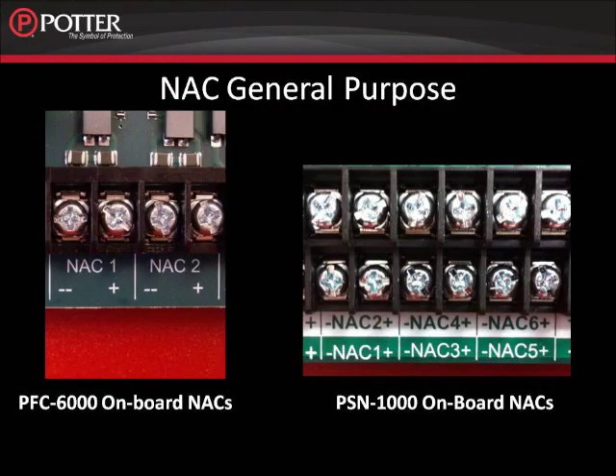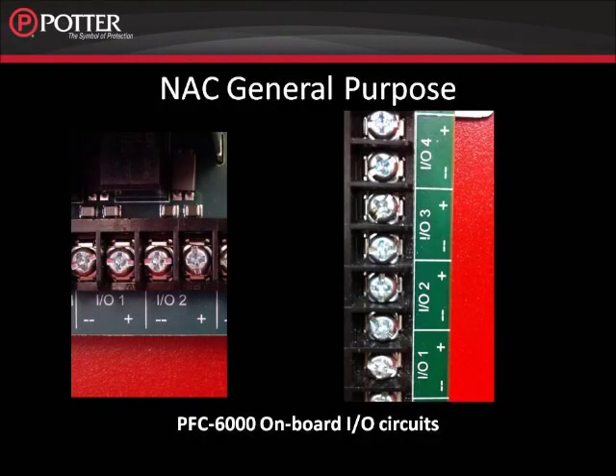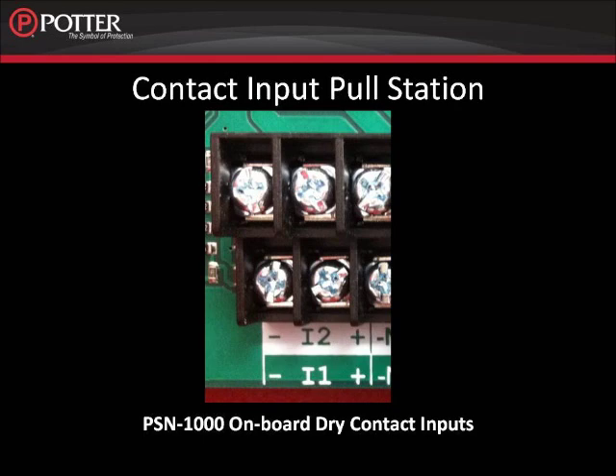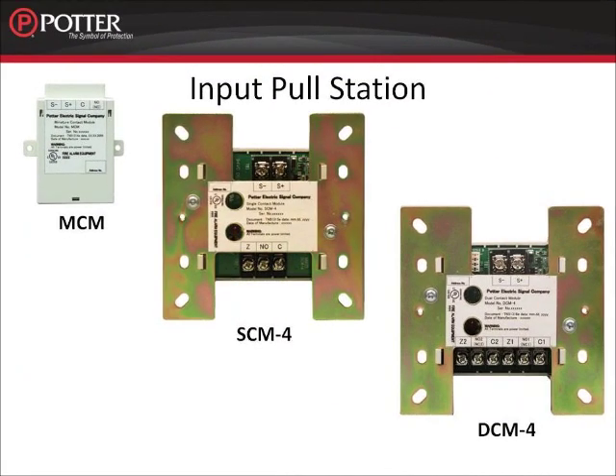The circuits labeled as NAC on the PFC 6000 series panels and the PSN 1000 power supply are initially configured as NAC general purpose. The circuits labeled as I-O on the PFC 6000 series panels are also initially configured as NAC general purpose. The two dry contact inputs on the PSN 1000 power supply are initially configured as input pull station. The MCM, SCM, and DCM are all configured as input pull station during the initial LEARN process.